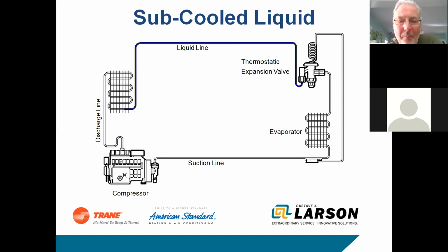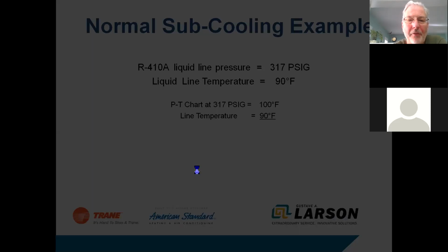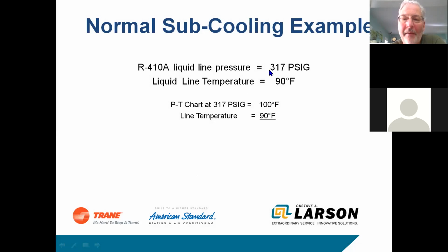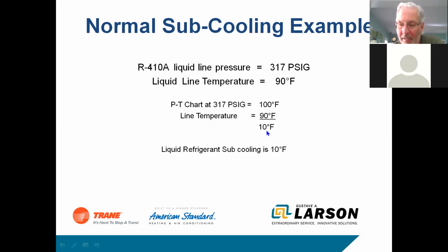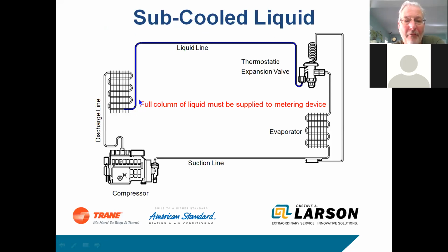Okay, so for proper subcool, we want to make sure that if the system is, here's a good example. If I have 317 pounds of refrigerant, that equates to 90 degrees, okay? So that's the temperature pressure chart relationship. I'm sorry, that equates to 100 degrees. So the PT chart at 317 is 100 degrees. If I read the liquid line and I see 90 degrees, that's telling me I have 10 degrees of subcool. And 10 degrees of subcool, if you look at this, means that I've got a full column of liquid feeding the expansion valve, okay?